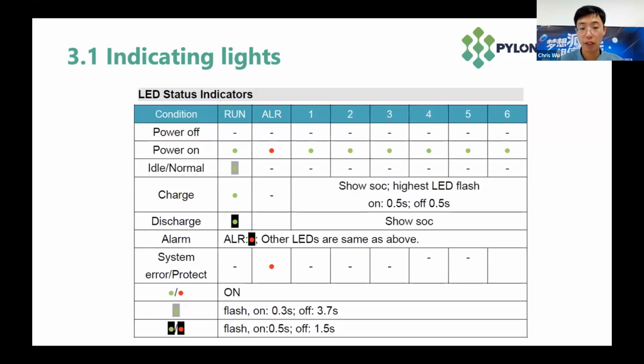When the battery has some alarm, like when the voltage is high or low, the alarm LED will flash, but the battery function is still normal. When the battery enters protection mode or has a serious problem, the alarm LED will be on and all other LEDs will be off, indicating to the customer that the battery needs to be checked.